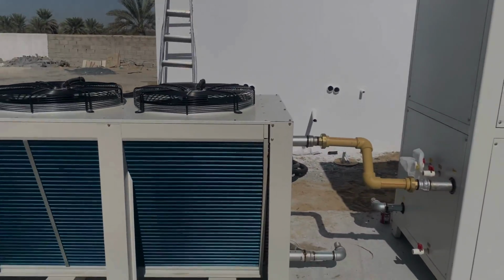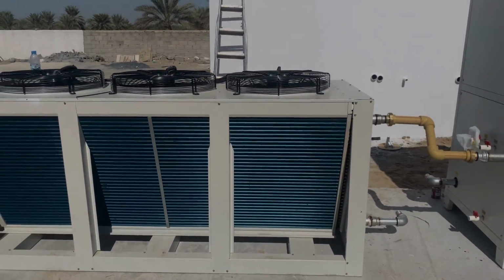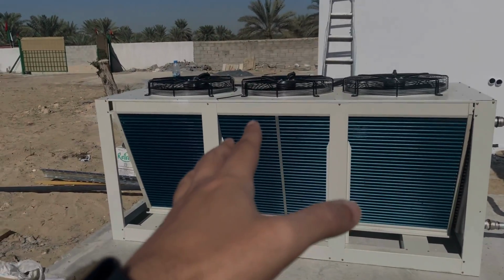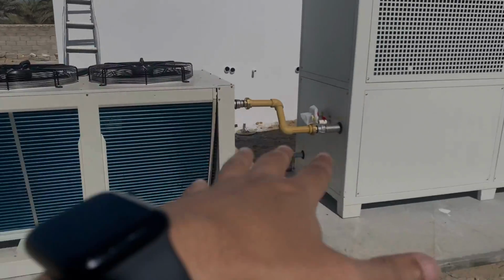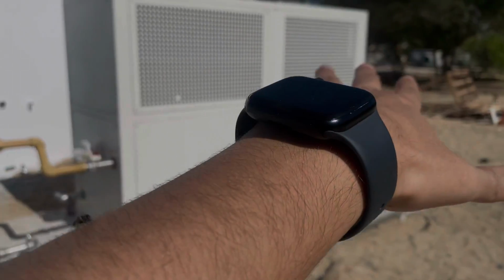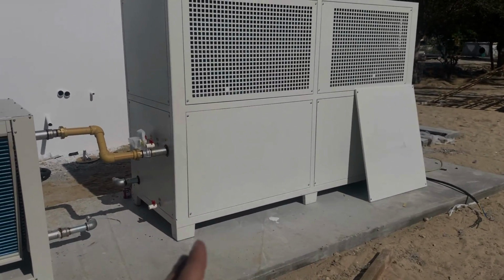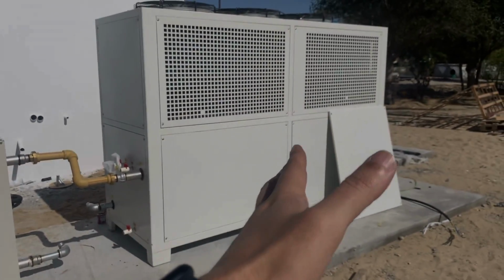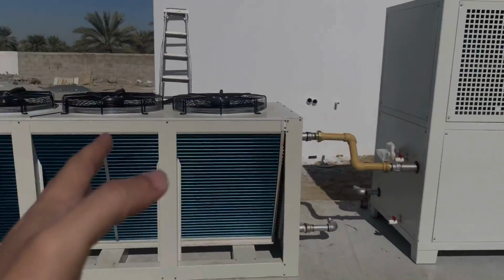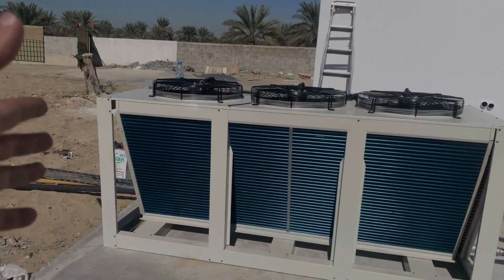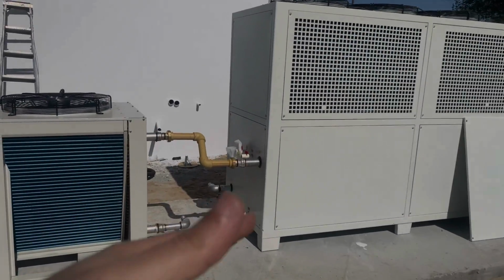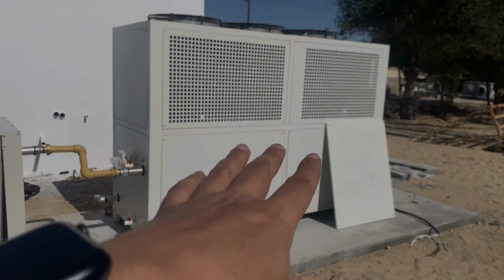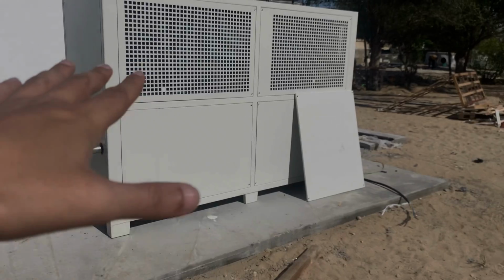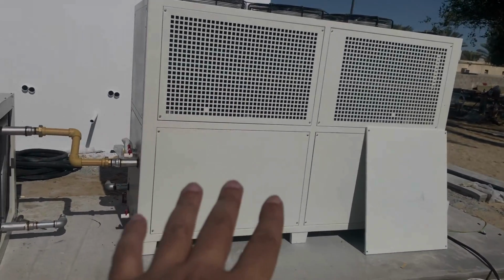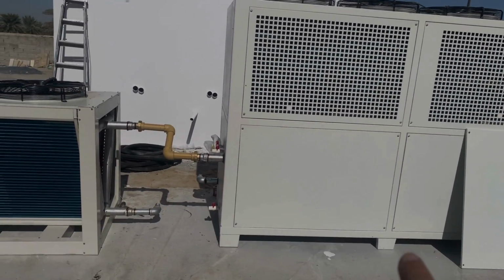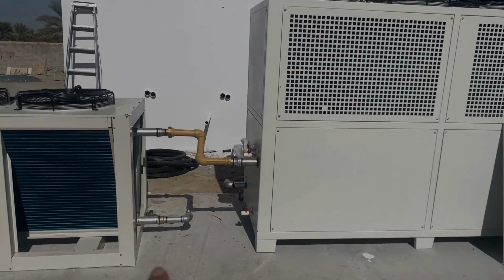During the cool seasons, we can use this dry cooler for cooling. If the target temperature, which we can set on the chiller, is reached and the cooling is enough, the compressors from the chiller will not kick in, so we will only be using the dry cooler itself. As soon as the temperatures go up, the compressors from the chiller will kick in and will cool the water even further to supply cooler water to the system.